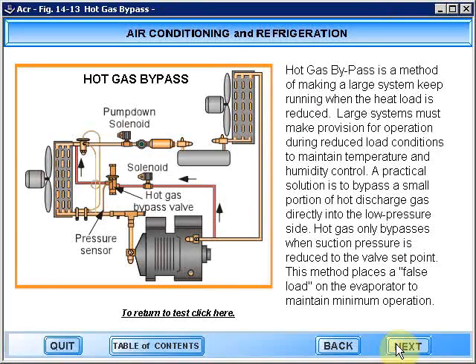Hot gas bypass is a method of making a large system keep running when the heat load is reduced. Large systems must make provision for operating during reduced load conditions to maintain temperature and humidity control. A practical solution is to bypass a small portion of hot discharge gas directly into the low pressure side. Hot gas only bypasses when the suction pressure is reduced to the valve set point. This method places a false load on the evaporator to maintain minimum operation.